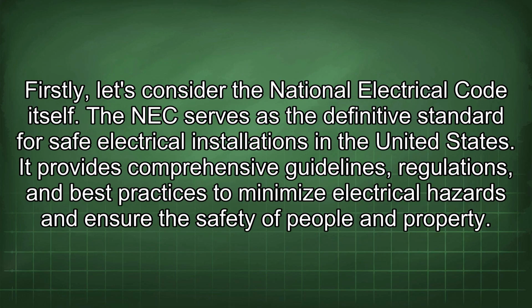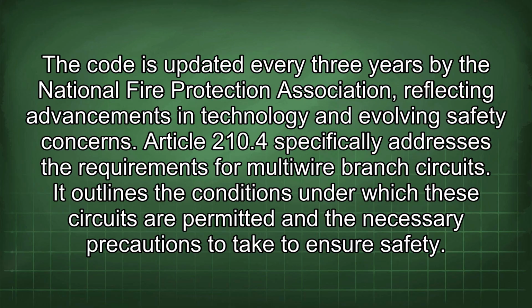Firstly, let's consider the National Electrical Code itself. The NEC serves as the definitive standard for safe electrical installations in the United States. It provides comprehensive guidelines, regulations, and best practices to minimize electrical hazards and ensure the safety of people and property. The code is updated every 3 years by the National Fire Protection Association, reflecting advancements in technology and evolving safety concerns. Article 210.4 specifically addresses the requirements for multi-wire branch circuits. It outlines the conditions under which these circuits are permitted and the necessary precautions to take to ensure safety.